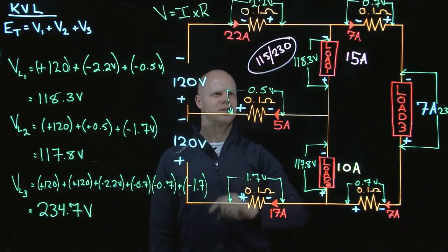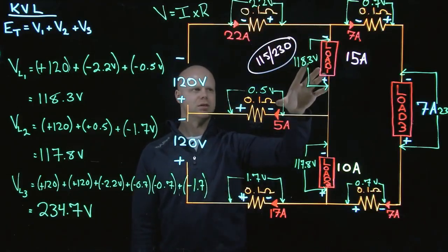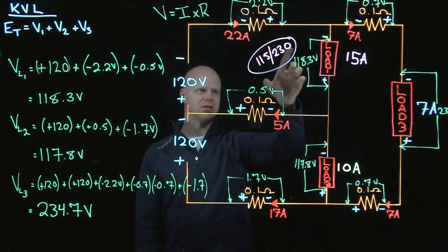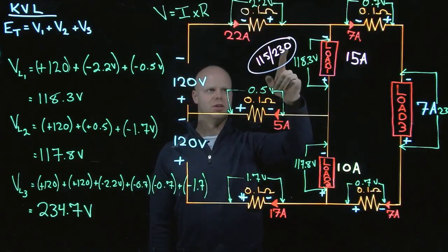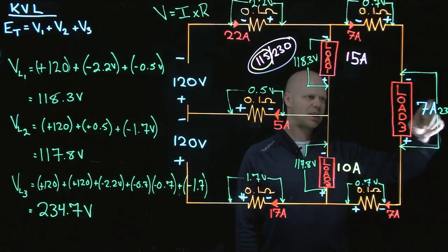So why do they give this voltage rating to a piece of equipment that theoretically we would apply 120 volts to? What they're doing is after my line loss, after my volt drop that exists across the conductors, I would still have slightly over in this case, but that's not a dangerous situation. Okay, that's just fine. I will have essentially rated voltage across my load, therefore I will get rated output. So I used in this case a 115 volt load, and I have relatively 115 volts, 118.3, I'll have rated output. This load back here, I connected it to my line 1 and line 2, or my negative, my positive terminal. It would have a rating of likely 230, close to 240 volts, probably 230 again. Do I have close to rated voltage? Absolutely. 4.7 volts excess is nothing we have to worry about when we're talking about ratings.